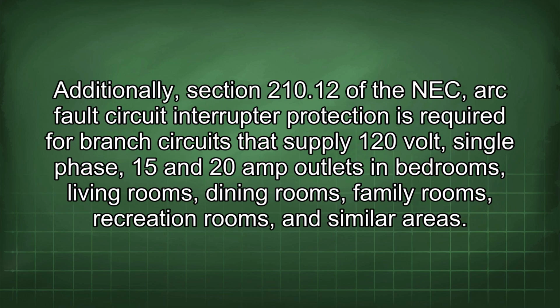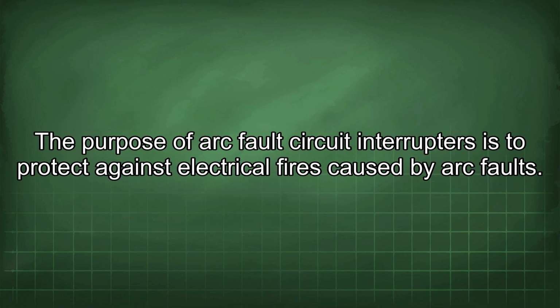Additionally, in Section 210.12 of the NEC, arc fault circuit interrupter protection is required for branch circuits that supply 120V single-phase 15 and 20 amp outlets in bedrooms, living rooms, dining rooms, family rooms, recreation rooms, and similar areas. The purpose of arc fault circuit interrupters is to protect against electrical fires caused by arc faults.